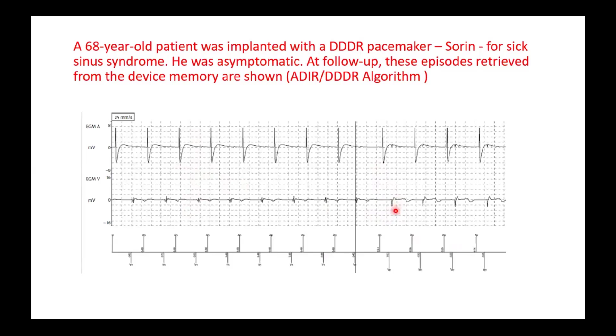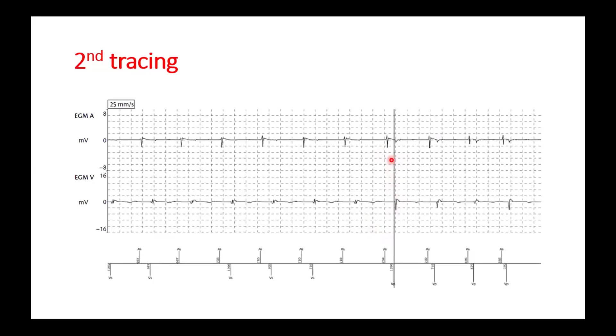Here is another situation. A pacing, V sensing, atrial pacing, but no V sensing. So the device considers this ventricular undersensing as a blocked beat. And when it occurs twice, atrial pacing and V pacing occurs due to a mode switch to DDD.